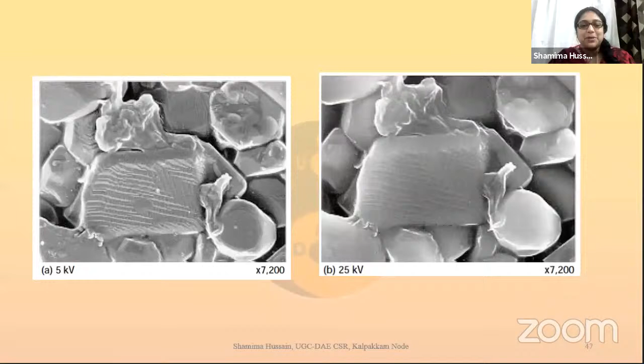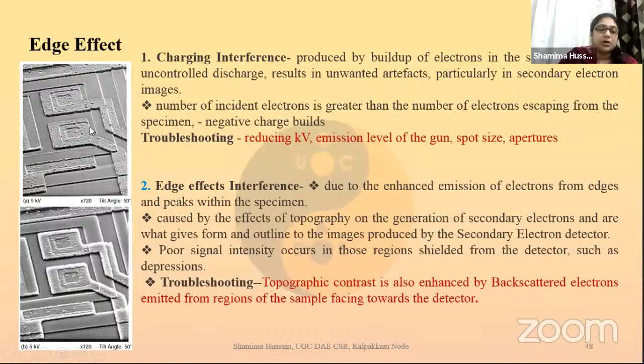And there are also edge effects. Edge effect is interference for features, related to the depth of focus we discussed. If the features are slightly higher like this, there will be interaction and scattering at the edges, interference of the electrons coming from the edges, and that is where the image appears blurred. Features very close to it would not be visible. So what do we do in such cases? A solution would be to reduce the voltage and try to see the images.